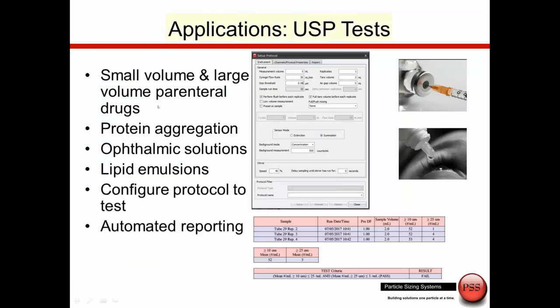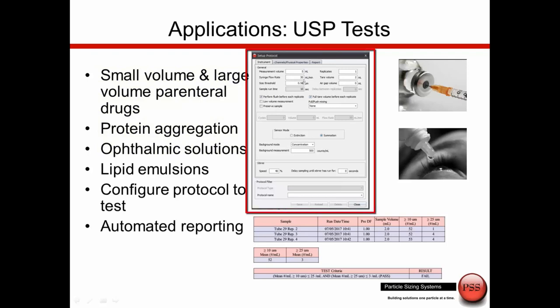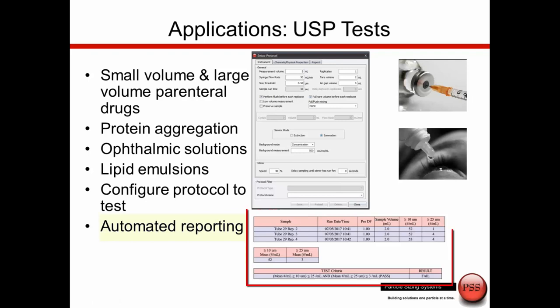The AccuSizer SIS is used in the pharmaceutical industry to look at large and small volume parenteral drugs, protein aggregation, and ophthalmic solutions — samples where we want to minimize the number of particles. It's used as a liquid particle counter to quantify the number and size of particles in what should be very clean fluids. The software protocol defines the size range, sample volume, and mixing parameters. Automated reporting includes a USP 788 report showing the number of particles greater than 10 and 25 microns and automatically calculating pass/fail criteria.